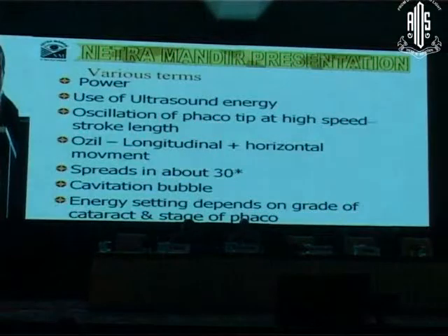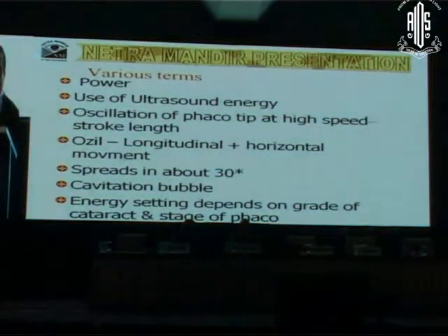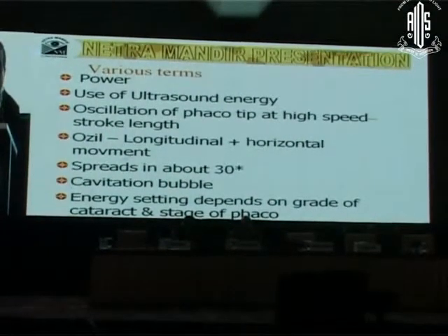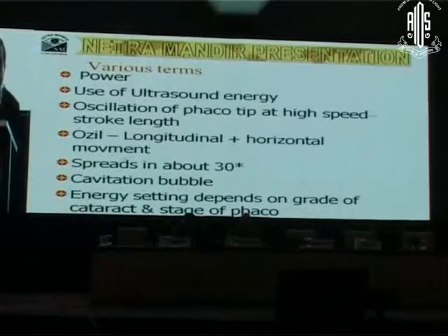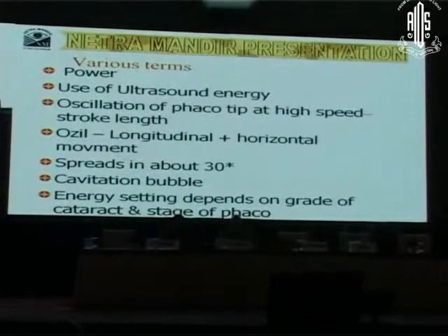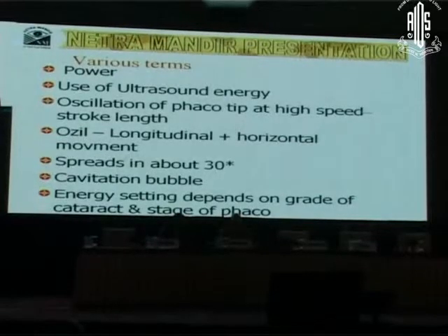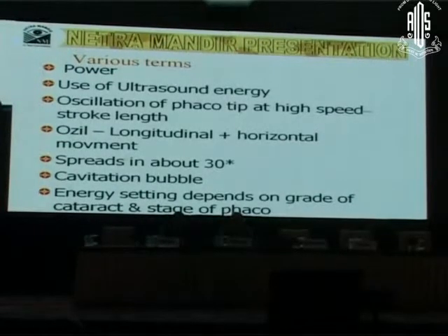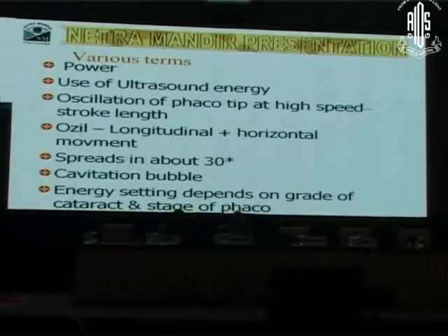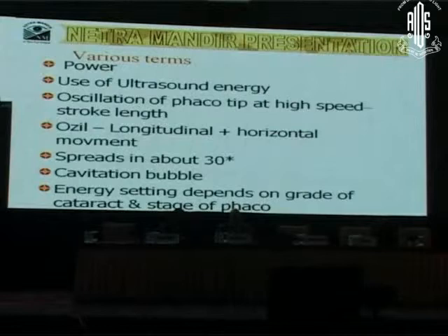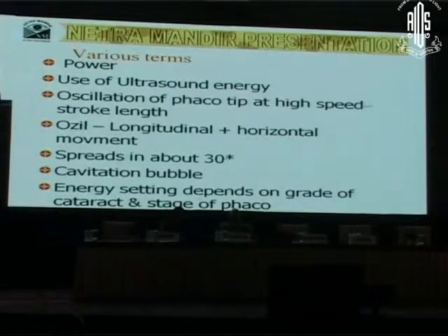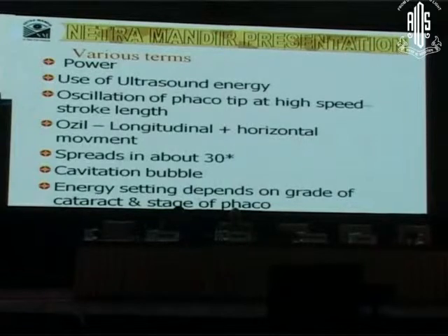However, in Ozil, which came up a little later, you had both longitudinal as well as horizontal movement. It's vitally important to remember that the energy spreads at an angle of about 30 degrees, and hence, if you do the phacoemulsification procedure in the bag, you will not damage the endothelium of the cornea to a large extent. Besides this, there are some machines which are believed to also act on a cavitation bubble, which I will come to a little later.